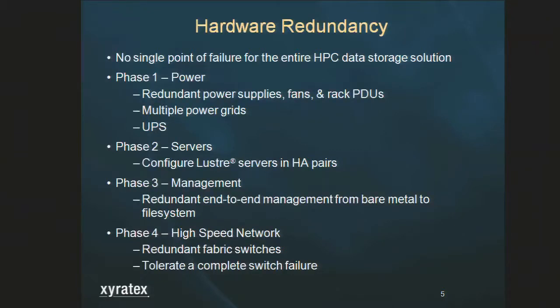Secondly, if you're integrating the solution into a rack, then having redundant rack PDUs and possibly redundant power grids into those rack PDUs lets you survive a catastrophic power outage of one power grid, so you can still service data in those cases as well.